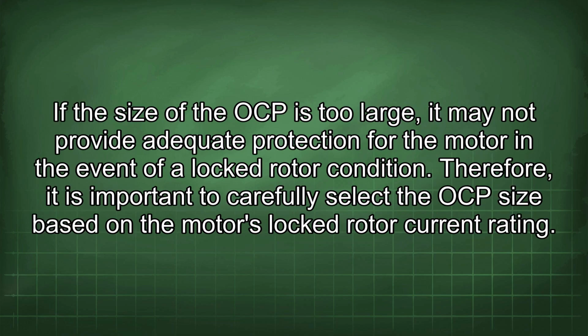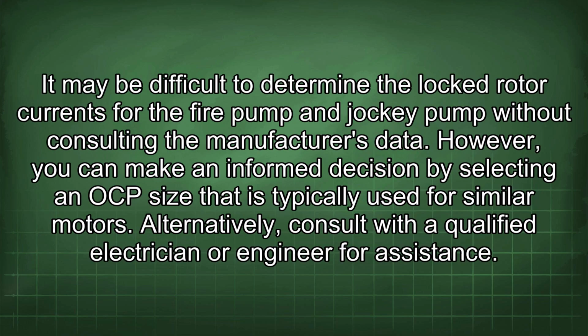If the size of the OCP is too large, it may not provide adequate protection for the motor in the event of a locked rotor condition. Therefore, it is important to carefully select the OCP size based on the motor's locked rotor current rating. It may be difficult to determine the locked rotor currents for the fire pump and jockey pump without consulting the manufacturer's data. However, you can make an informed decision by selecting an OCP size that is typically used for similar motors. Alternatively, consult with a qualified electrician or engineer for assistance.